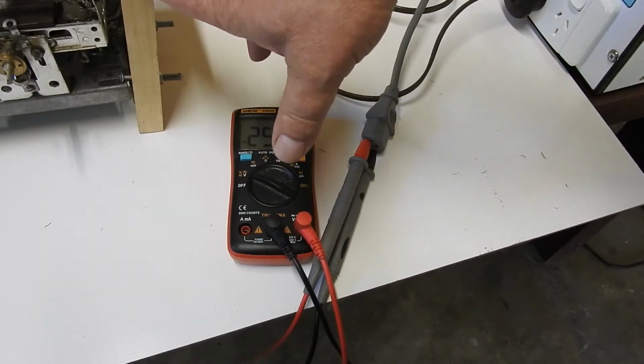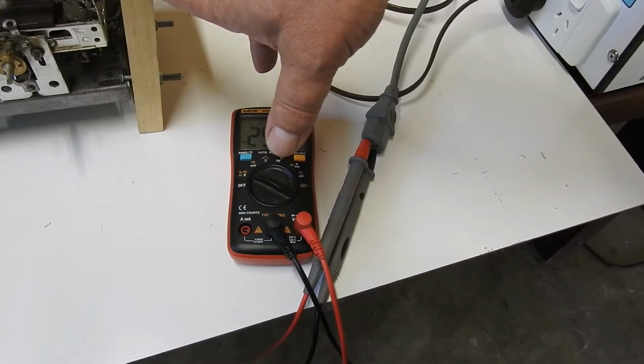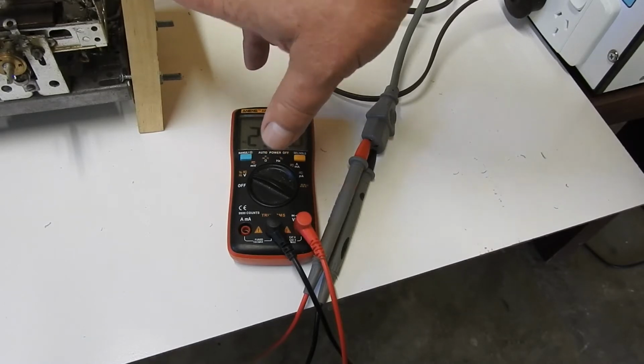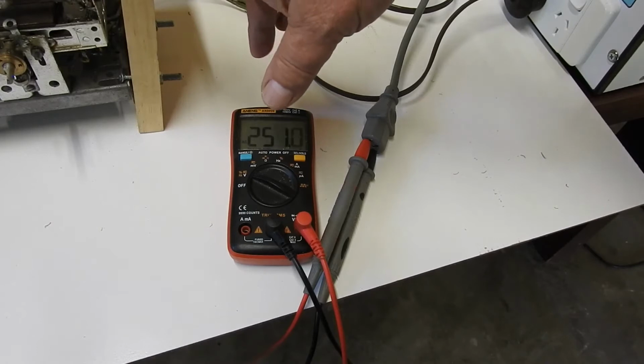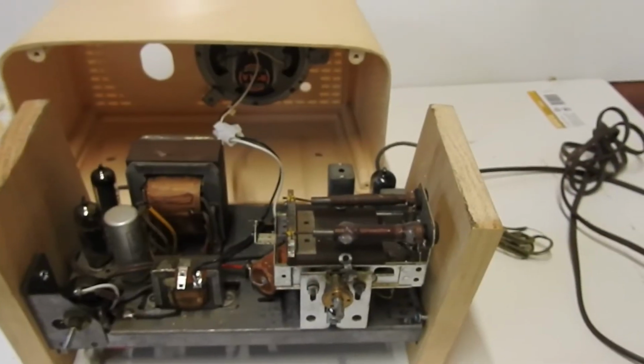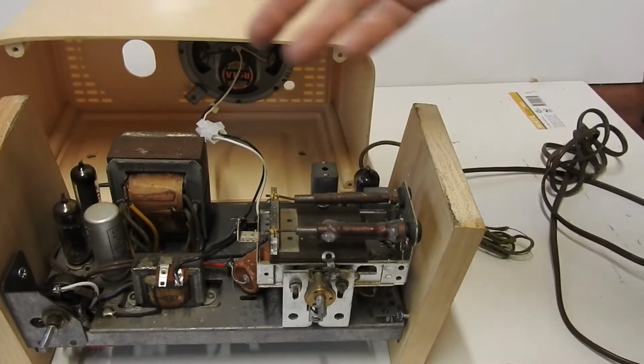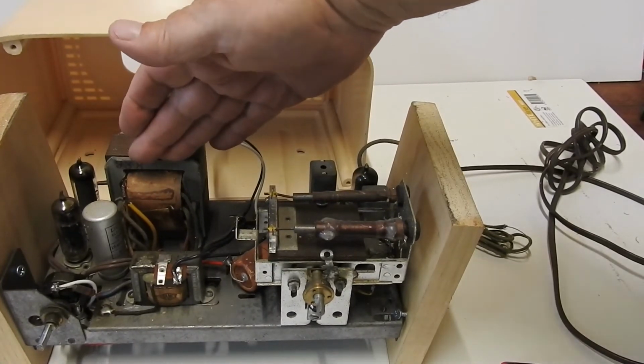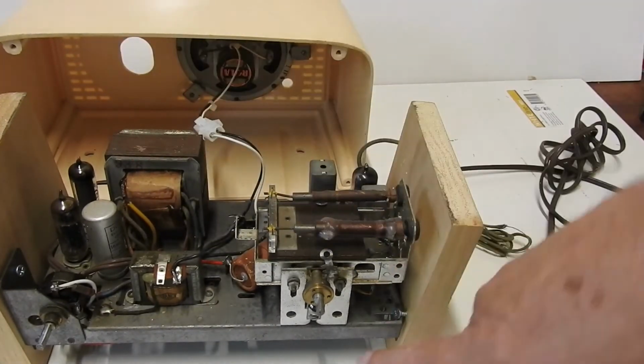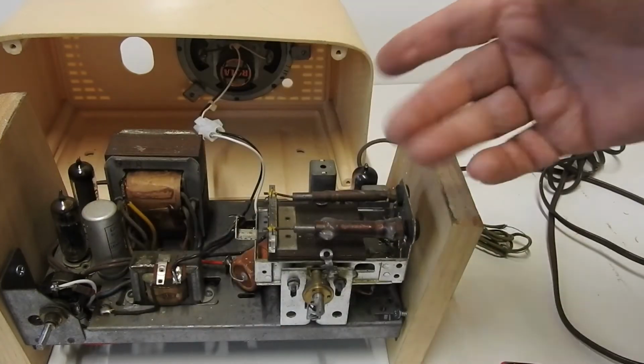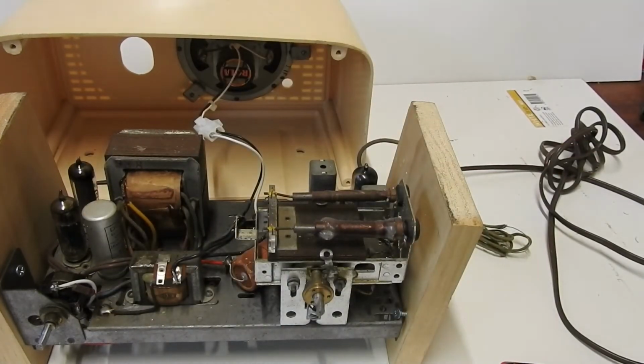The radio is rated 200 to 250 volts, I think, which is quite a range, but 250 volts is at the extreme end. I'm suspicious that since there's no regulation, 250 volts goes straight into this transformer, and the 6.3 volts that lights up the globe and the filaments - that's probably fine at a nominal 230 volts input, but at 250 it's probably a bit high and things just don't last as long. So I want to try and mitigate that.